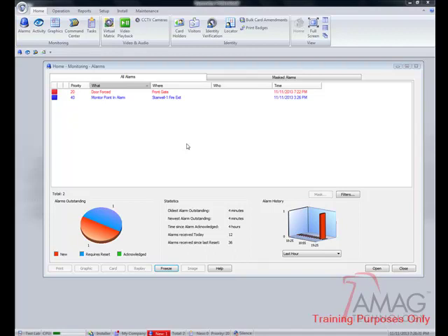Masking alarms does not affect its status as indicated by the red, green, or blue colors. Masked alarms can be opened, acknowledged, and cleared in the same way as unmasked alarms. Masked alarms are included in activity reports but are not included in the total number of unacknowledged alarms. Alarm forwarding, as set up in the Operation Alarms routing screen, is disabled for masked alarms. The person who masked an alarm can be determined from the comments information in the alarm details.